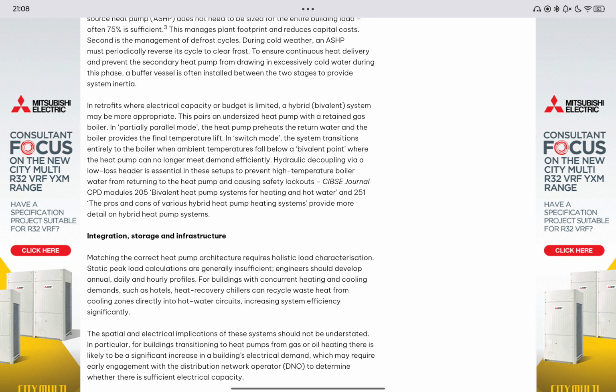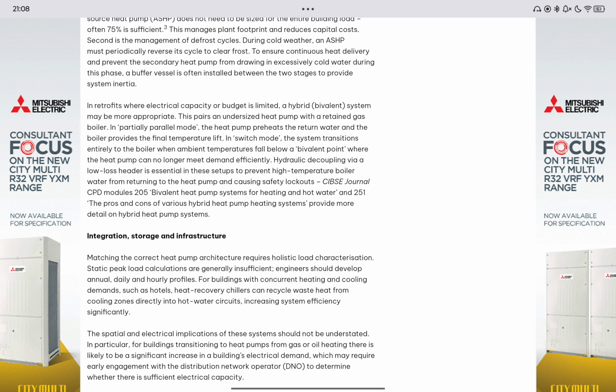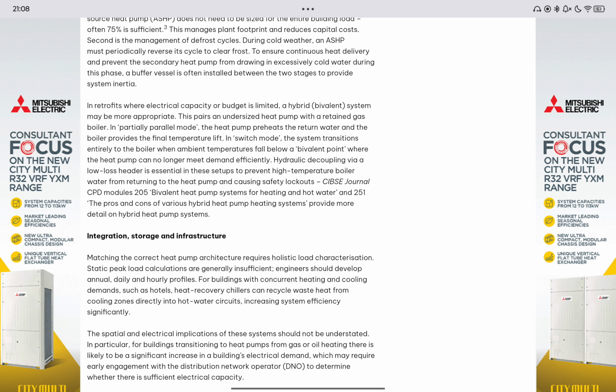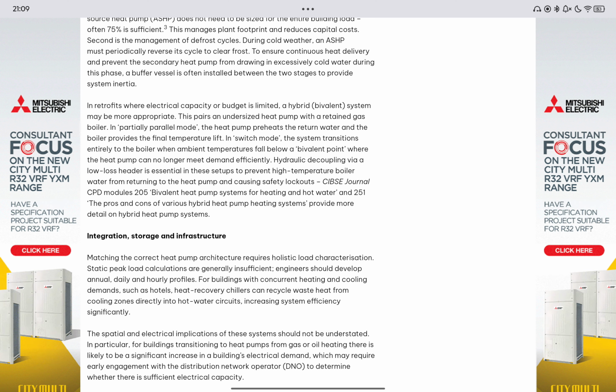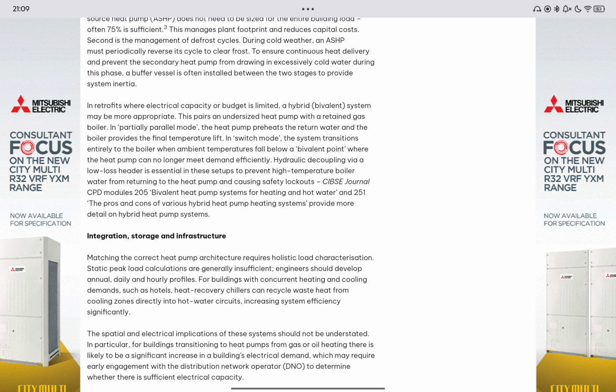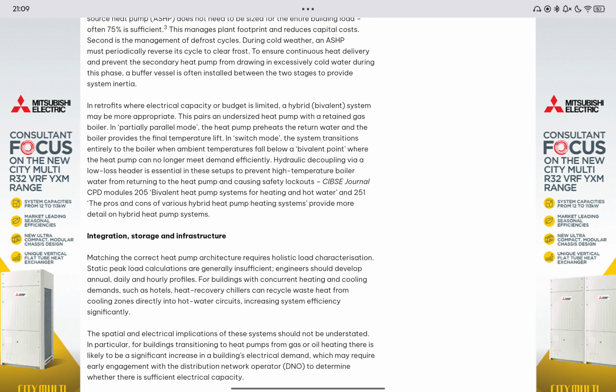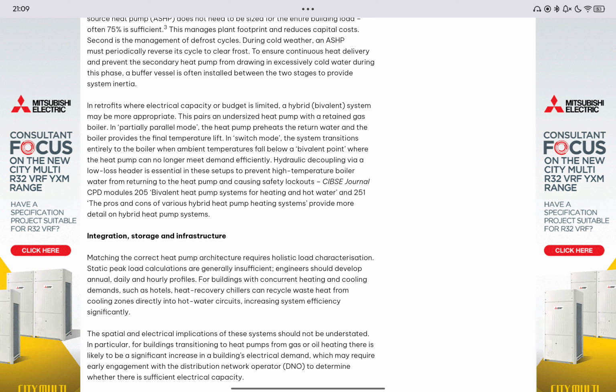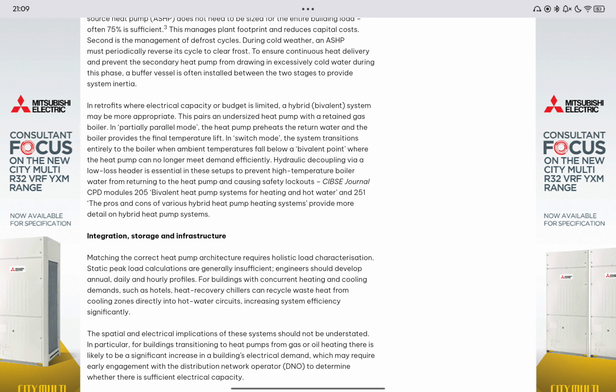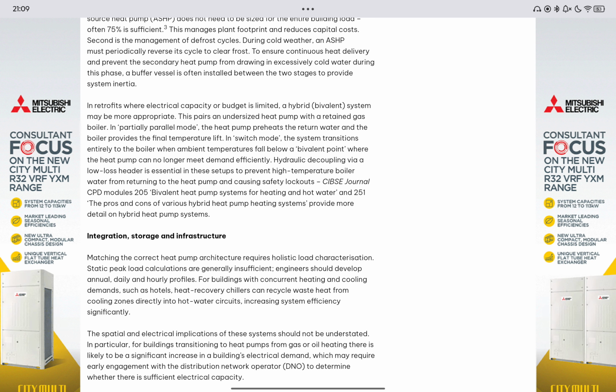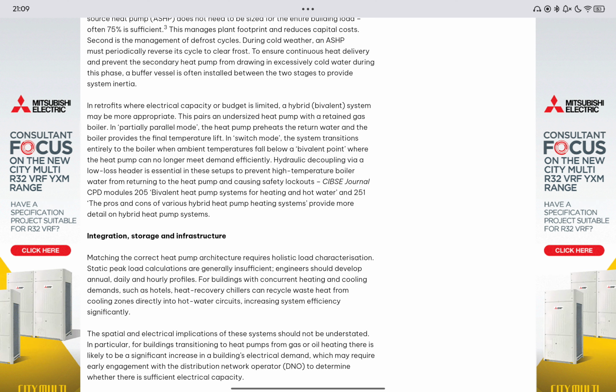In retrofits where electrical capacity or budget is limited, a hybrid or bivalent system may be more appropriate. This pairs an undersized heat pump with a retained gas boiler. In partially parallel mode, the heat pump preheats the water, and the boiler provides the final temperature lift. In switch mode, the system transitions entirely to the boiler when ambient temperatures fall below a bivalent point, where the heat pump can no longer meet demand efficiently. Hydraulic decoupling via a low-loss header is essential in these setups to prevent high temperature boiler water from returning to the heat pump and causing safety lockouts.